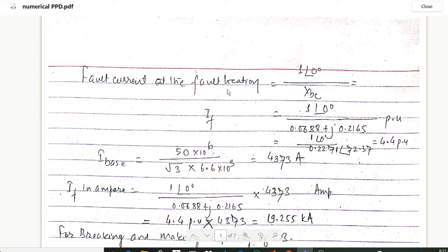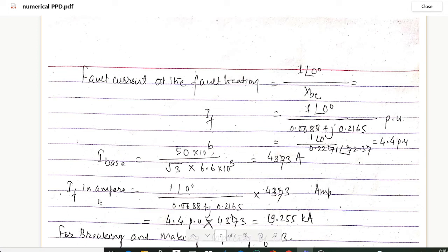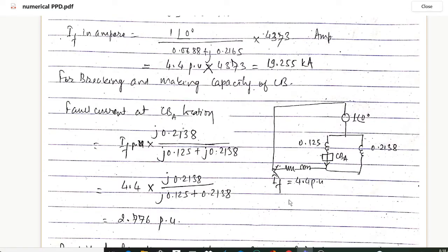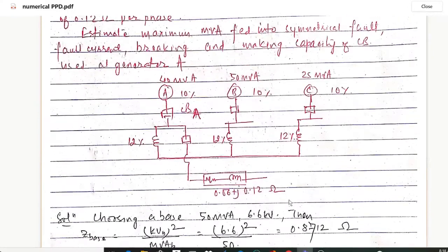The fault current at the fault location is: I_f = 1∠0° / X_BC = 1 / 0.2271∠72.37° = 4.4 per unit. The base current is I_base = 50×10⁶ / (√3 × 6.6×10³) = 4373 A. Therefore the actual fault current is 4.4 × 4375 = 19,255 A or approximately 19.255 kA.